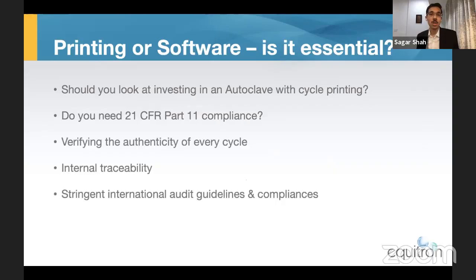Laboratories now are requiring some form of cycle record and historical records as well for internal traceability requirements and audit trails. Regulatory bodies might also ask you for your autoclave cycle records to verify the authenticity of the tests conducted, as well as validate whether your tests have been conducted as per the autoclaving practices that are recommended.